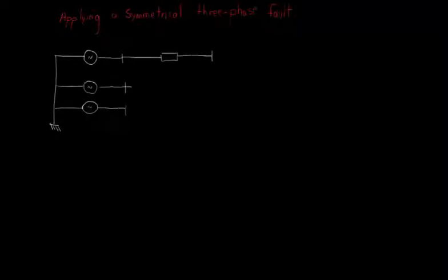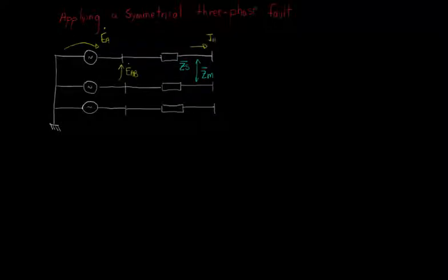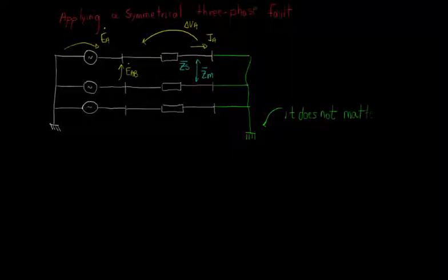Let's start applying symmetrical three-phase fault at the end of the Thevenin equivalent, something like this. Notice that it doesn't matter if the fault is grounded or not, because the three-phase fault is symmetrical. Let's label the current on phase A as the three-phase short-circuit current ISC3. Remember that EAB is equal to square root of 3 times EA with a displacement of 30 degrees, because we are assuming that the three-phase voltage source is symmetrical.